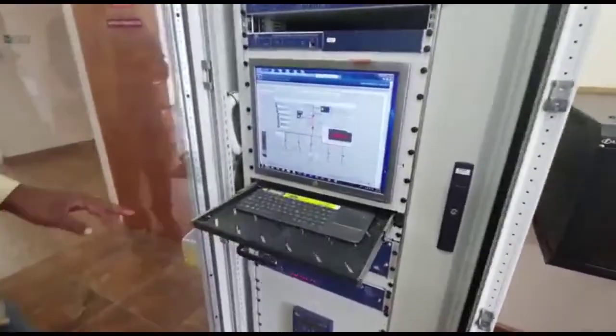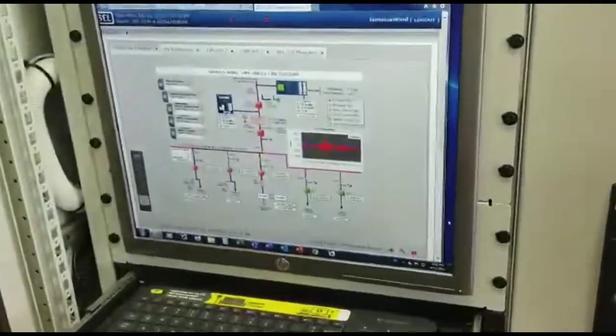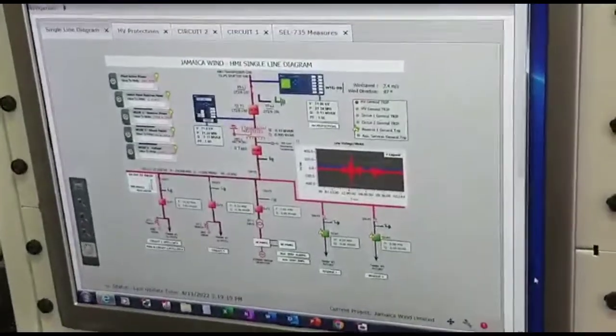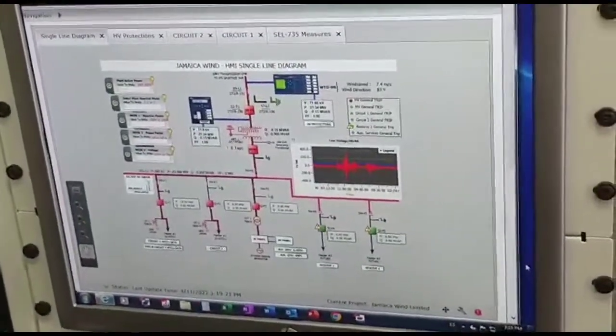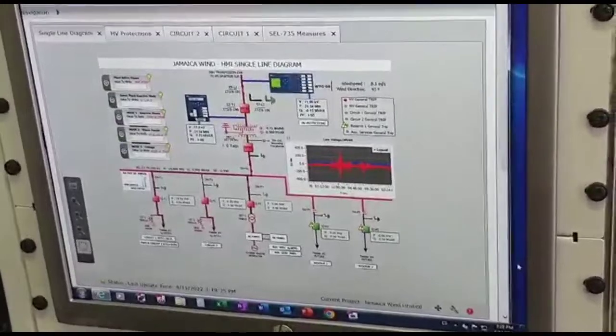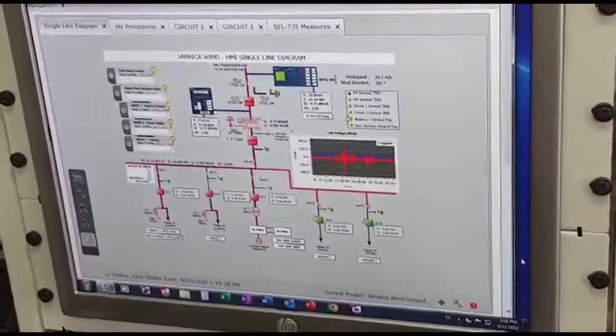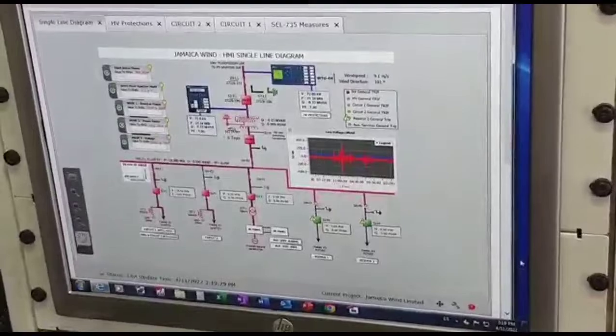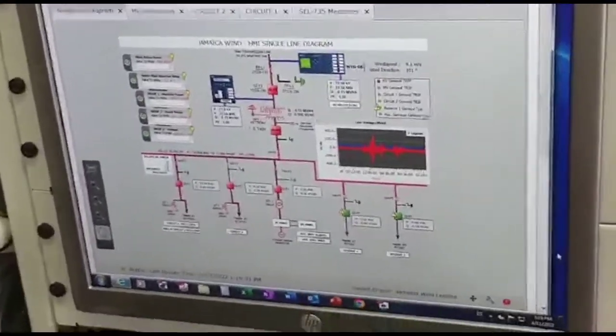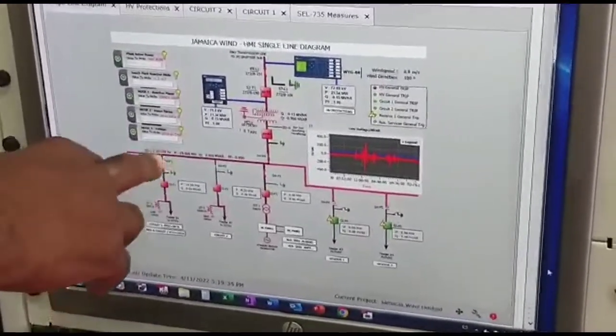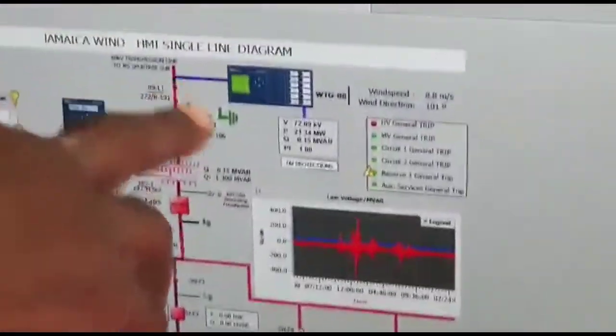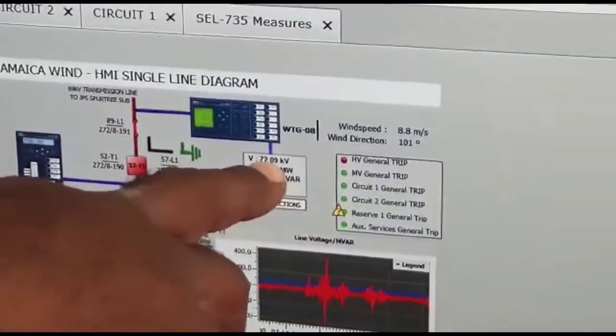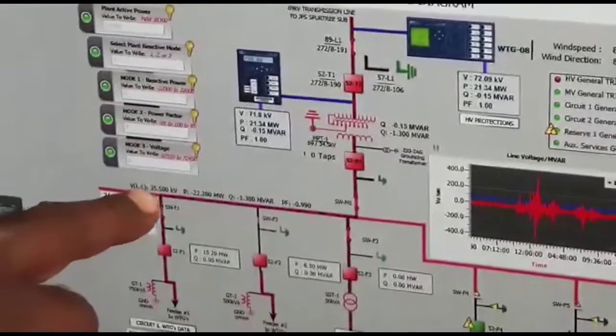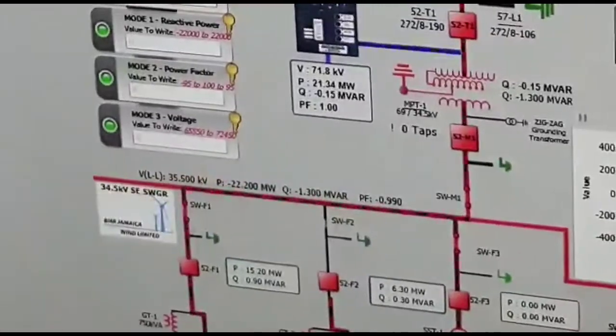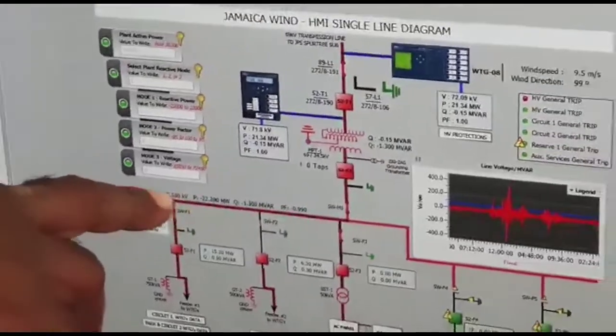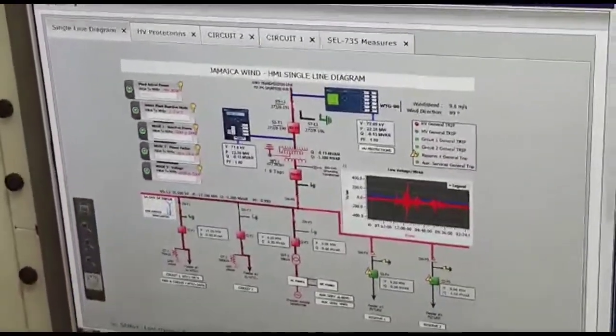So here we have an HMI computer, and it gives you the most relevant, current information that you need to know about what is happening in all the circuits inside the entire plant. Here we have the low side, and here we have the high side. Currently the high side is at 72.09 kV, and the low side is at 35.5 kV, meaning that we are actually running a bit higher than we should.